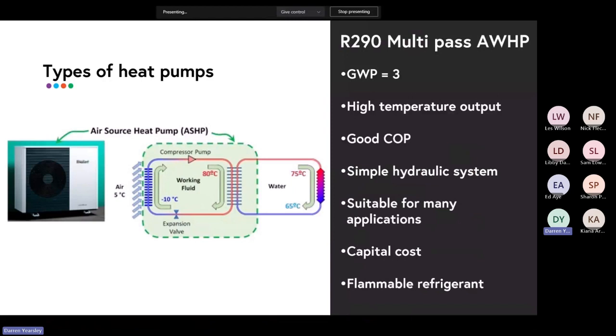So the advantages of your R290 in this multi-pass becomes kind of apparent, where you can design your system much more like you would a gas boiler, indirect gas boiler based system. You can have your hot water storages in parallel rather than in series. And so if you've got 3,000 litres of water stored, all 3,000 litres of water when you've finished your recovery cycle will be at 65 degrees. So now you can deliver that all in one hit into your building in a much more consistent way.